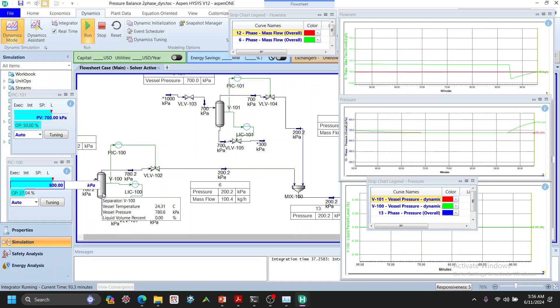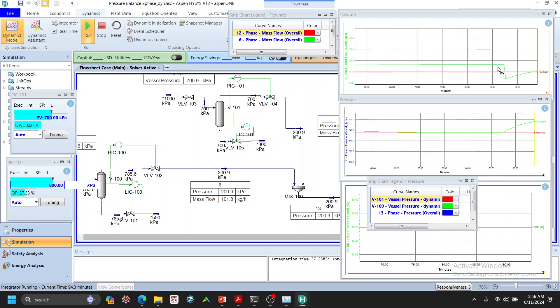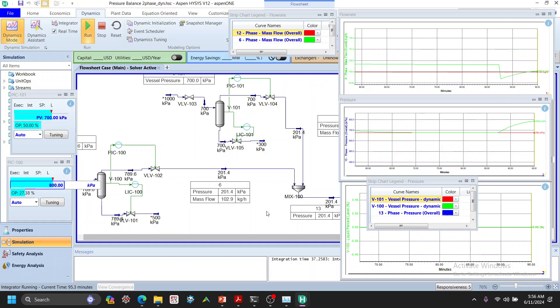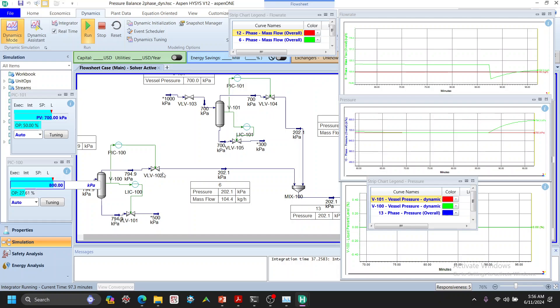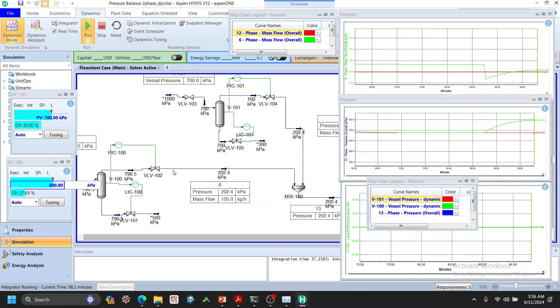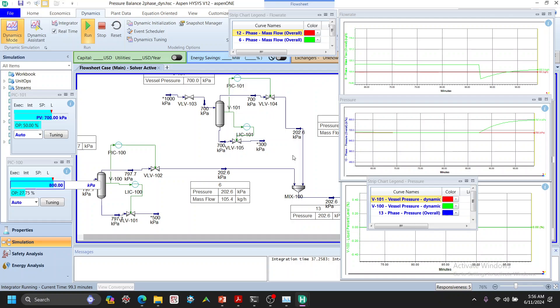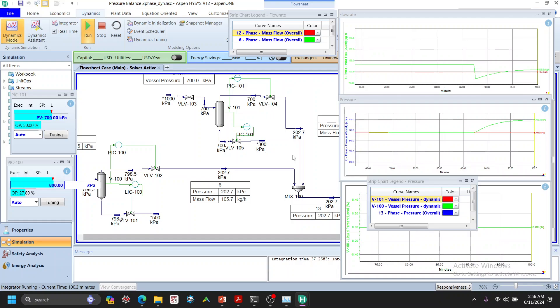The flow rate drops a little bit and then starts to recover while the vessel pressure is rising toward the new set point of 800 kPa. Following the same logic, the delta-P across this path will increase from 500 to 600 kPa as the vessel pressure rises from 700 to 800 kPa. So we'd expect a higher steady-state flow rate on this line compared to the other one — that's our prediction for now.